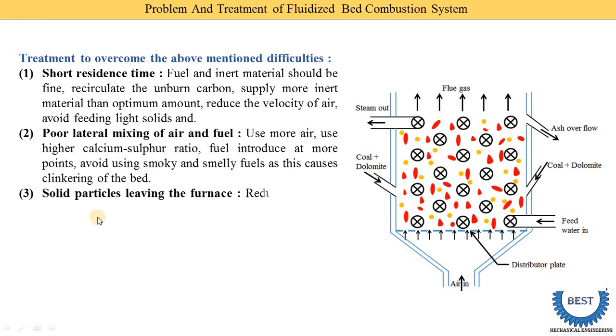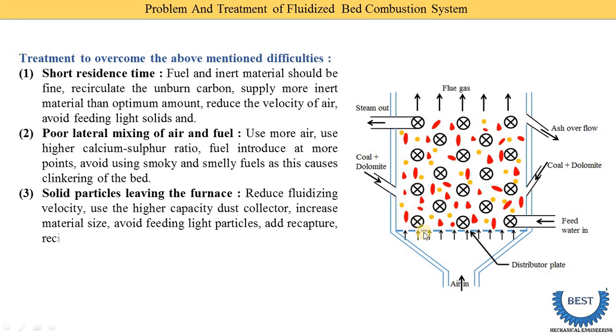The third problem is solid particles leaving the furnace — coal and dolomite in solid state leave the furnace before combustion is carried out. To avoid this, we need to reduce the fluidizing velocity, meaning we reduce the velocity of the fluidizing air. Also, use a higher-capacity dust collector. Increase material size — if the material size is larger, its weight is also higher, so the particles do not leave with the flue gases.